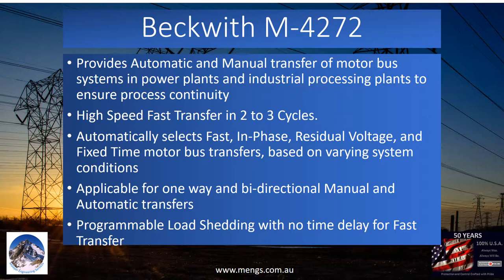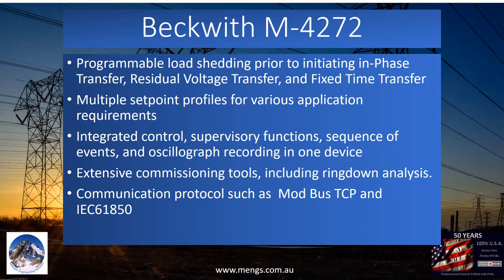Highlight features include: high-speed fast transfer in 2 to 3 cycles; automatically selects fast, in-phase, residual voltage, and fixed time motor bus transfers based on varying system conditions; applicable for one-way and bi-directional manual and automatic transfers; programmable load shedding with no time delay for fast transfer; programmable load shedding before initiating in-phase transfer, residual voltage transfer, and fixed time transfer; multiple set point profiles for various application requirements; and integrated control, supervisory functions, sequence of events, and oscillography recording in one device.